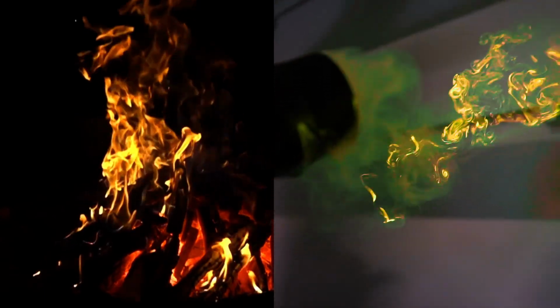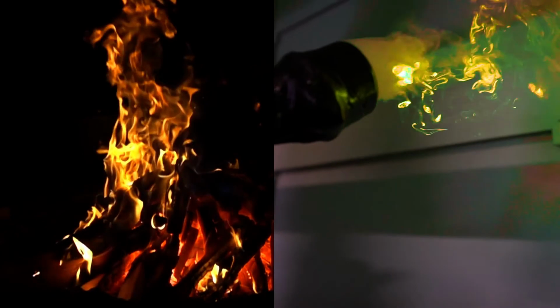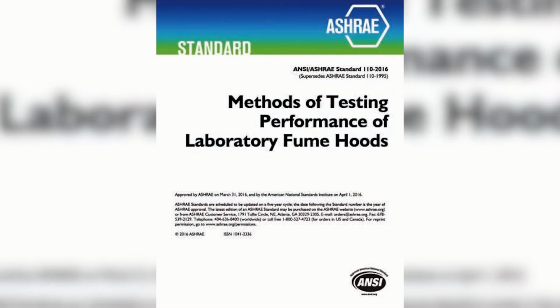You've probably seen fume hood tests published by manufacturers. These tests are valid and useful, but you should understand how the tests were performed. Fume hoods are rigorously tested at the factory to ensure their performance. Fume hood manufacturers do the ASHRAE 110 AM, or as manufactured, test with an empty hood in a test room under perfect room conditions. The reason for this test is to separate the hood's performance from the influences of the room. This allows you to do an apples-to-apples comparison of various hoods, but it doesn't tell you how that hood will perform in your lab.